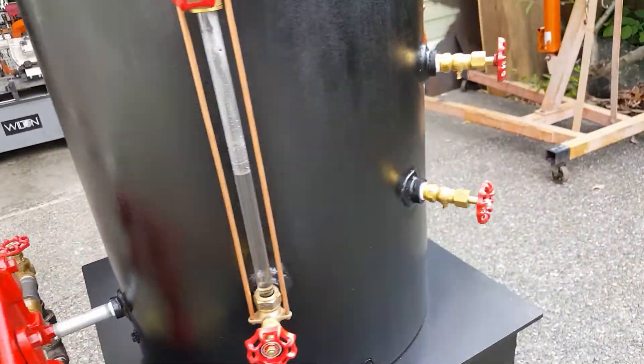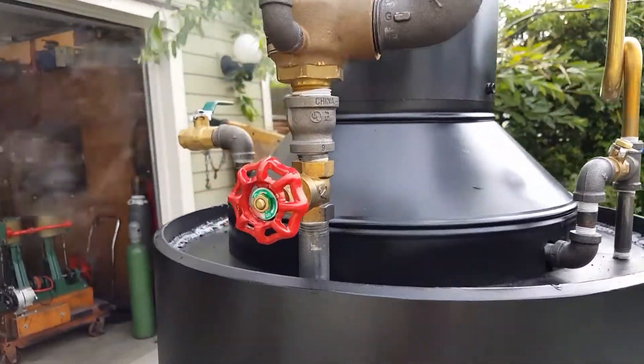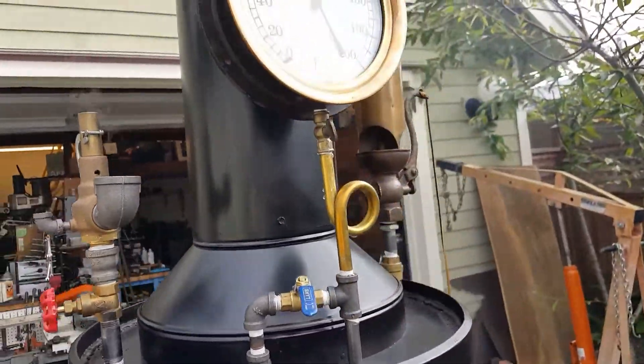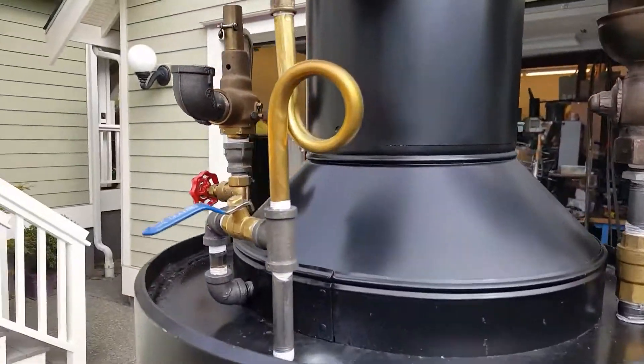Sight glass, Hyco, pop-off valve set at 100 pounds. I have temporary valves on them to make sure the pop-off valve works properly. Really nice gauge — I think it's an 8-inch gauge. Brass siphon on it.